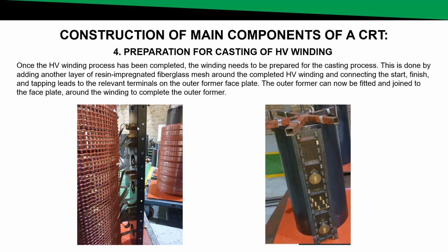There are some typical examples of the resin on the outer layer fitted outside the windings. There are the tappings going to the relevant tapping sections and the start and the finish of the transformer. And then there's the completed jacketed high voltage winding ready to go to the casting process.